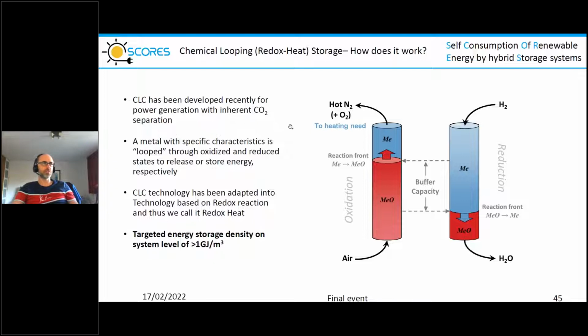Historically, chemical looping, or CLC technology, has been developed for power generation applications where separation of CO2 takes place, and it's based on metal oxidation and reduction processes, as is our approach here. The technology has been adopted from industry toward the built environment and scaled down significantly to be applied in buildings. Its major advantage over many other storage technologies is its inherent high energy density, which on system level should reach values well above 1 gigajoule per cubic meter. In comparison, hot water reaches about 0.15 to 0.18 gigajoules per cubic meter.